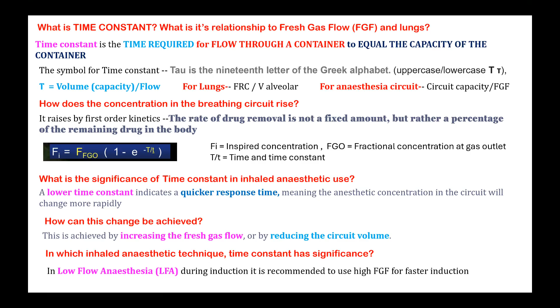So from this point of view of low flow anesthesia, for faster induction you need to know about this time constant. And another indication is pediatric induction, where you use a higher flow rate, and the pediatric circuit, especially the Jackson-Rees circuit, has a lesser volume. So the time constant can be achieved with a higher flow rate and faster induction can be achieved in children. So these are the two important indications for knowing about the time constant in this uptake discussion.